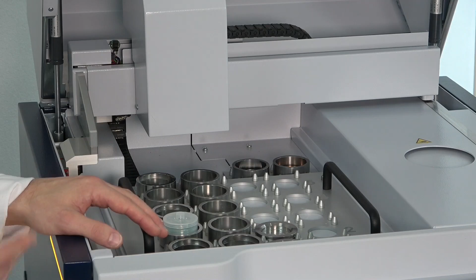On top of that, we also have additional positions here in the back, which are fixed for quality control. And these can also be automated and programmed so that operators do not even have to deal too much with quality control. This can happen automatically to monitor the state of the system and the status of the calibration itself.